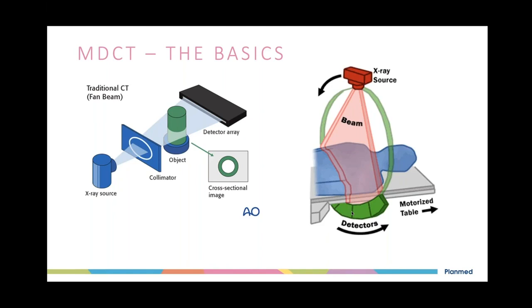The X-ray source in medical CT is a fan beam with multiple detectors, and it is constantly turned on and rotating while the motorized table moves the patient through that fan beam. The relative speed of the table in relation to the rotation speed of the X-ray source and the detectors is what gives the slice thickness, or the detail, of that medical CT image.